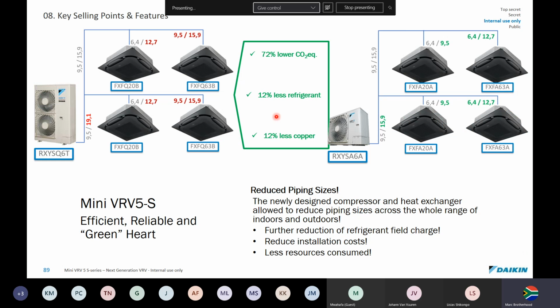And this is pretty much what I mentioned to you about the reduced piping sizes. The newly redesigned compressor and heat exchanger allow reduced piping sizes across the whole range of indoors and outdoors. There's also further reduction of refrigerant charge. You use smaller copper. It costs less for the person to install.